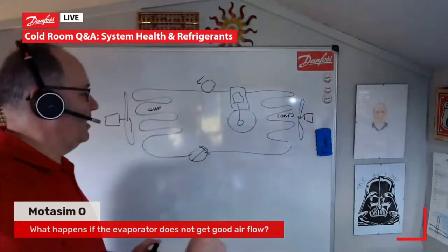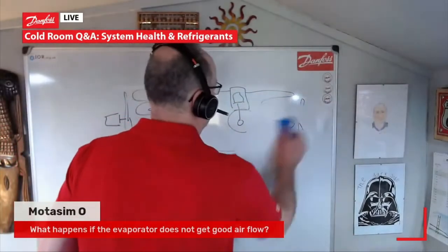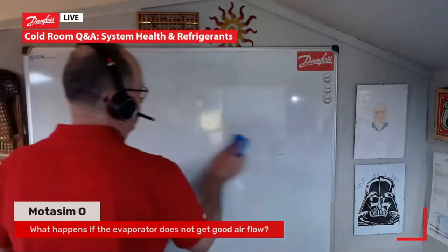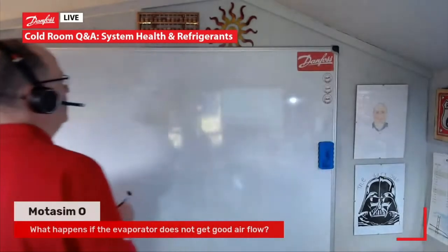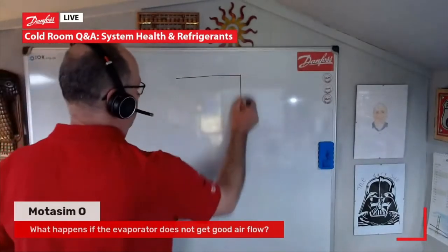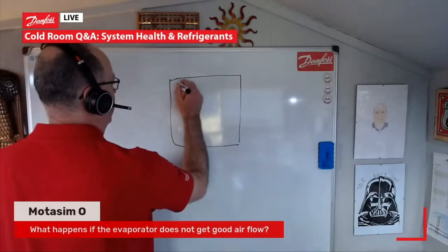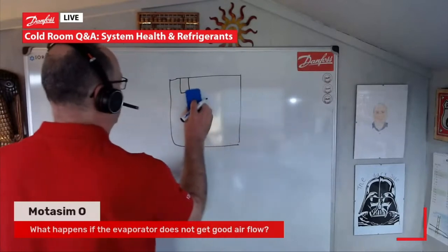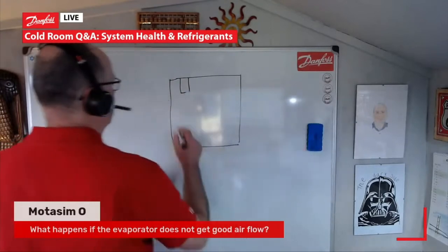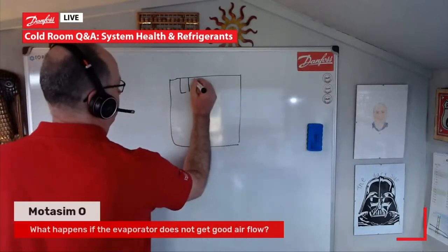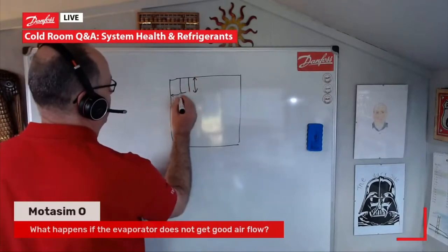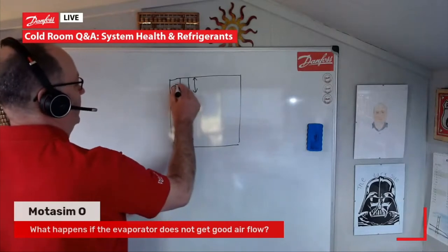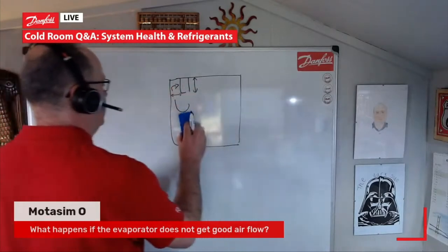Poor airflow can happen for many reasons. Probably the most common is storage issues within the cold room itself. Looking at our simple cold room, if we have our evaporator where it should be, the rule of thumb is generally that the clearance dimension at the back of the coil should match the evaporator's own dimension, so we get good airflow and don't have any issues.